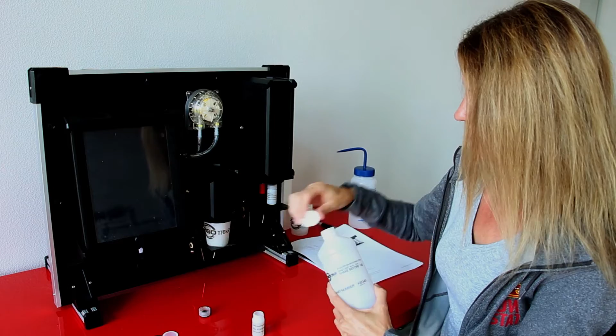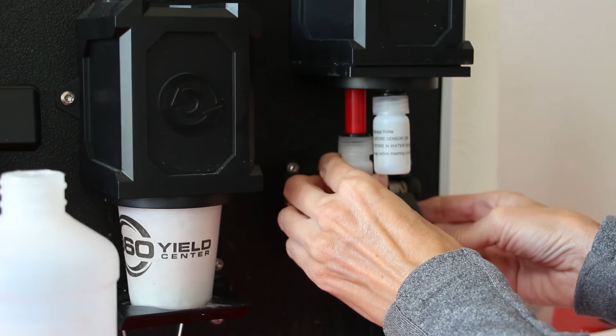Secondly, go ahead and take your reference electrode bottle, and from here we're going to store this one wet with some standard solution. So you can take your standard solution, which is your pH 7, fill this bottle up a little bit over half to three-quarters full. You can put the cap on loose on that one too, and then we're going to slide this one up here too on the red reference electrode. That one we do want it to soak.